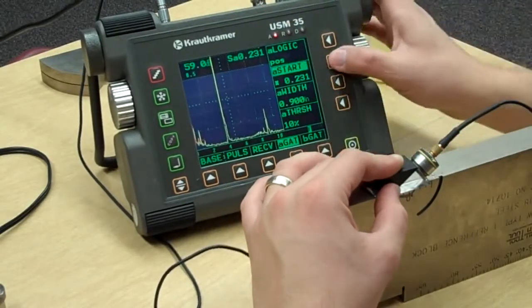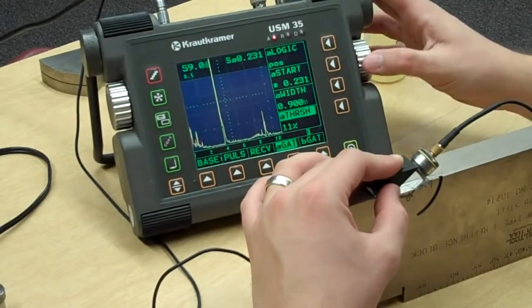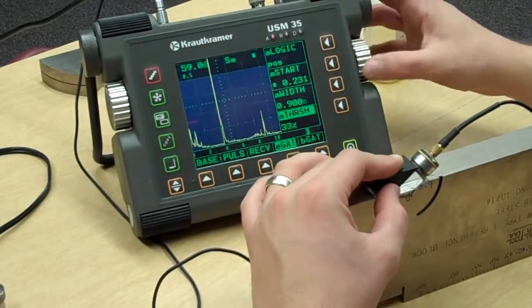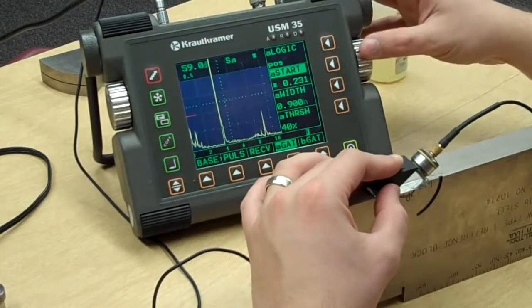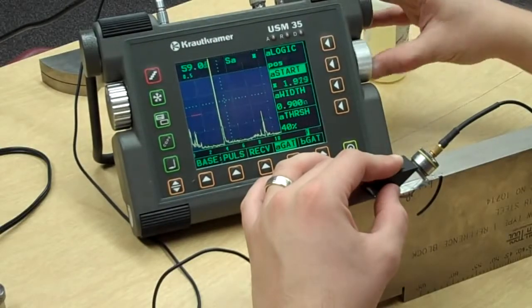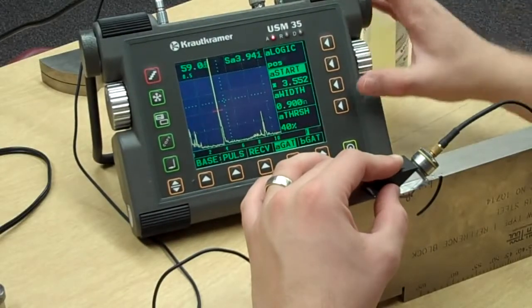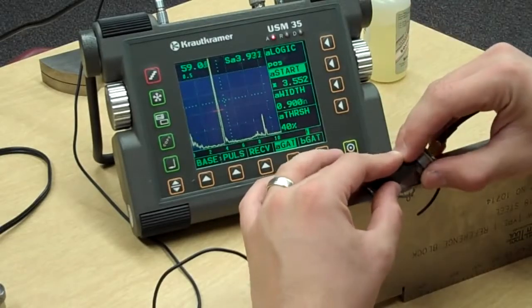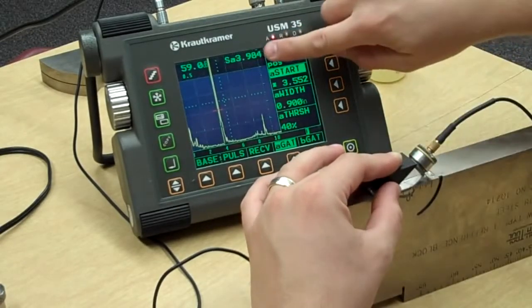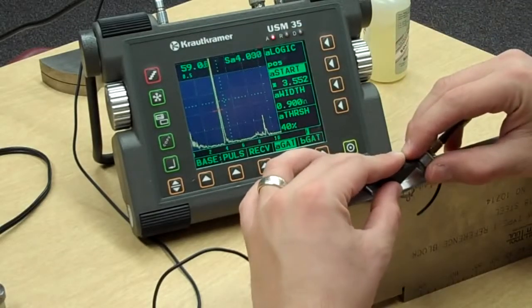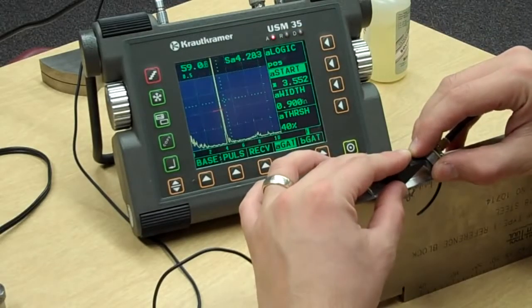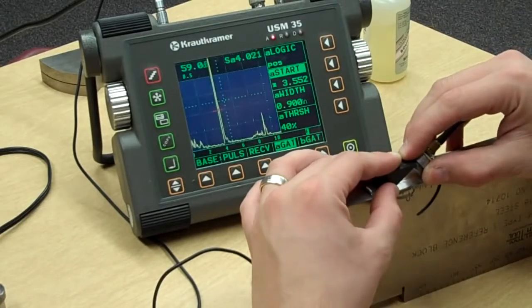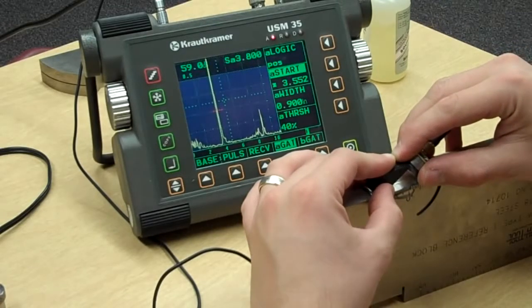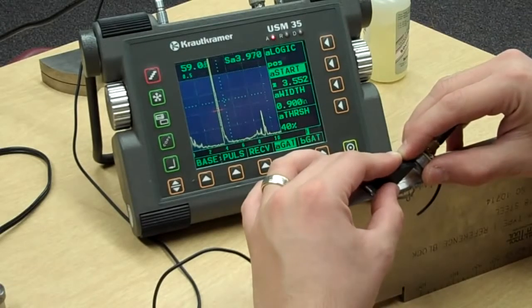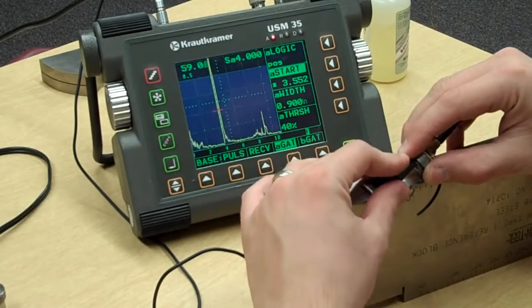So now, here's my gate. I'm going to raise this up to about 40% screen height, and I'm going to bring it over to where it touches that signal. Okay? Now if you watch this sound path, that SA, it's going to walk on us because I'm moving the transducer back and forth. So 4.283, 3.800 basically. I'm going to put him right on 4 inches. Okay, and I'm going to do the best I can to not move this transducer.